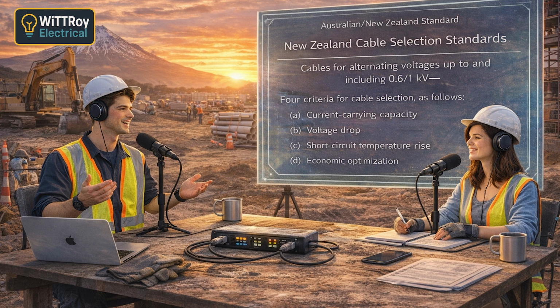Why is voltage drop a problem though? Think about a motor. Okay. What happens if the voltage is too low? It might not start properly or it draws more current? Exactly. It can overheat or fail. So we need to keep voltage within limits. Yes, and those limits are given in the wiring rules. So how do we calculate voltage drop?